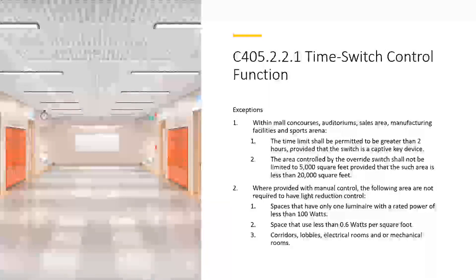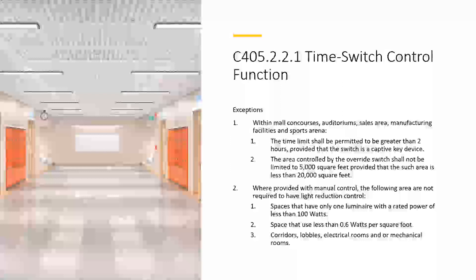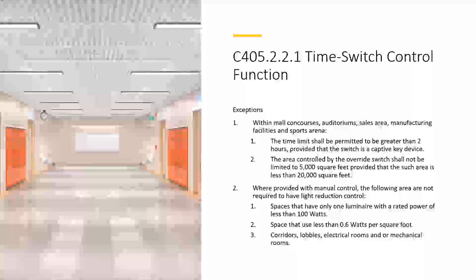Any individual override switch shall control the lighting area for not larger than 5,000 square feet or 465 square meters. The exceptions are mall concourses, auditoriums, sales area, manufacturers, and sports arenas — the area controlled by the switch is not limited to 5,000 square feet, provided such area is less than 20,000 square feet. Where provided with manual control, spaces are not required to have light reduction control if they only have one luminaire rated at less than 100 watts, spaces using less than 0.6 watts per square foot, or corridors, lobbies, electrical rooms, and mechanical rooms.